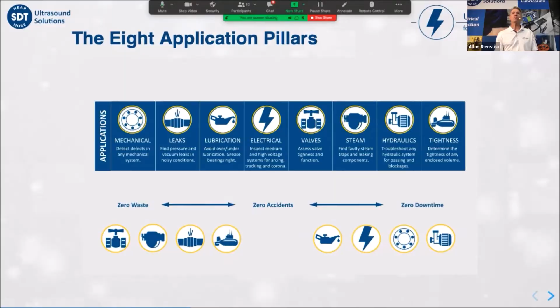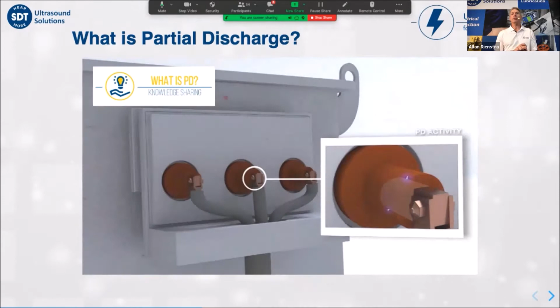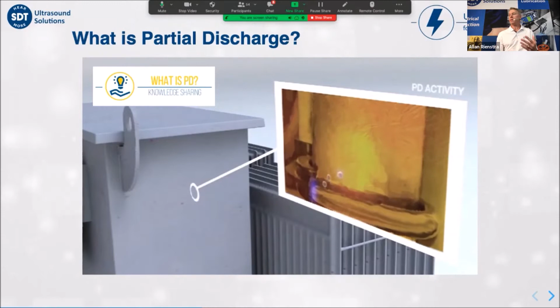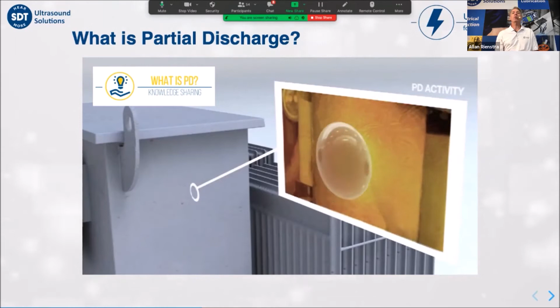Partial discharge is a localized electrical discharge or spark in an insulation system that doesn't completely bridge the gap between 2 conducting electrodes. It can occur at any point in the insulation system where the electrical field strength exceeds the breakdown strength of that portion of the insulating material. This could be due to voids within a solid insulation material. It could be across the surface of insulating material. It could be in these gas bubbles that you see here within liquid insulation, or around electrodes in gas in the form of corona.